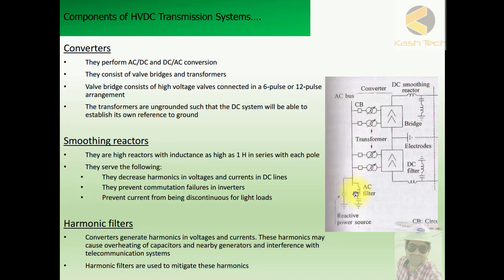The smoothing reactors serve the following purposes: they decrease harmonics in voltages and currents in DC lines, they prevent commutation failures in the inverter, and they prevent current from being discontinuous for light loads. They also limit fault current because when a phase-to-ground fault occurs, the reactor impedance is in the fault path and reduces the fault current.